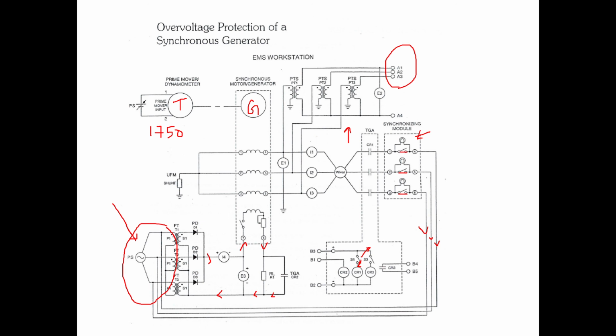When you open this contact, the resistance is included in the circuit, so the current will now flow through the resistance and will be reduced. When the current reduces, the over voltage will be reduced to the normal voltage. Here we have to learn two things. How to create a fault? The fault is created by manually opening CR1. What is the control action? The control action is to open this contact so that the current flows through the resistance and is reduced. When the excitation current is reduced, the voltage will automatically be reduced.